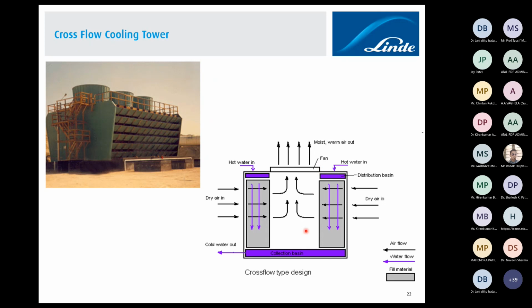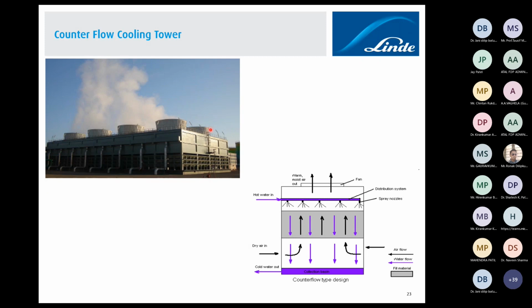Now let us understand what is happening in counterflow. This is a counterflow cooling tower, and here you can see dry air and water movement in opposite directions. The second thing you can see here is that it is not a gravity flow, it is pressure jetting. So you will find more atomization, which helps to improve the heat exchange, and this is why you are able to keep the height quite low, by 1 to 1.5 meters. For the same heat duty you can have a lower height cooling tower, which ultimately saves structure and capital cost.